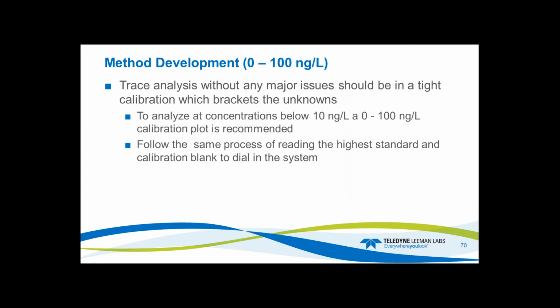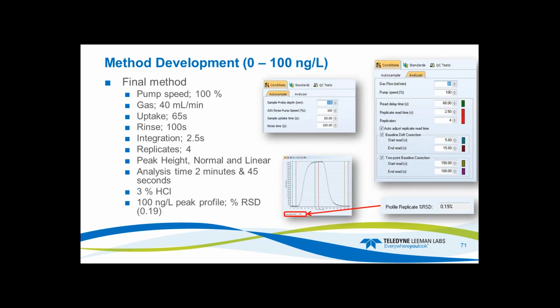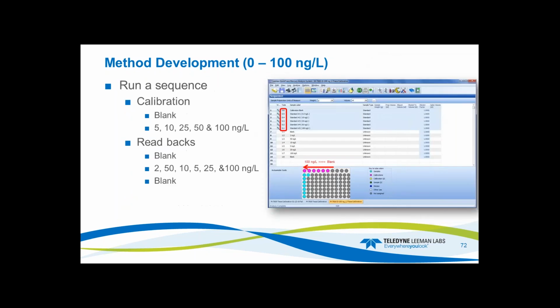Quickly, we'll look at 0 to 100. This is where we would go when we're working at trace to ultra-trace analysis. Typically, if you want to analyze below 10 ppt, 10 nanograms per liter, this is what you would use. So I followed the same, read the standard and so forth, opened up a method, set the pump speed to 100, gas flow 40, uptake 65, rinse, integration, peak height, normal linear, 2 minutes, 3% HCl was my rinse. 100 nanogram per liter peak profile, percent RSD is 0.19%. Great, that's a really nice peak profile.